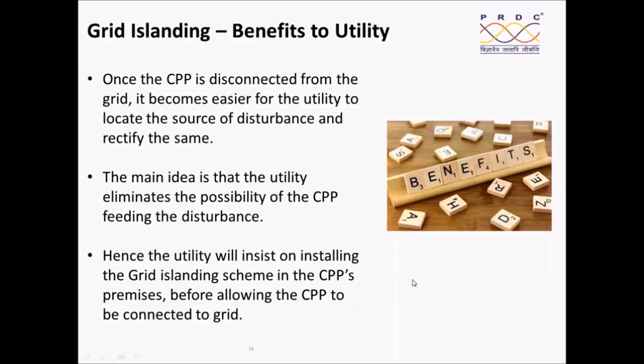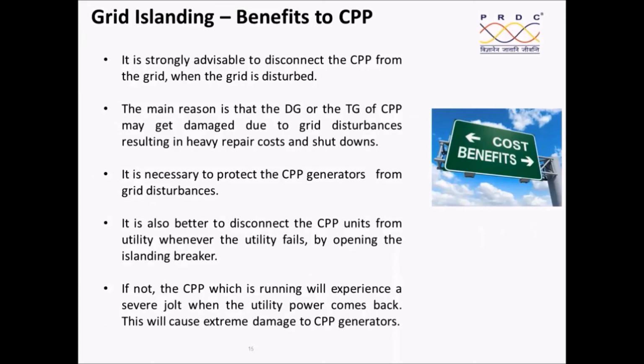The utility will insist on the installation of the grid islanding scheme so that the CPP gets separated out. This is very important for us to understand. What are the benefits to the captive power plant? The major grid disturbance and the uncertainty in the grid will not get reflected, and there is no major problem to the generators and the process. Therefore, the grid islanding is going to bring a lot of benefit to the captive power plant.